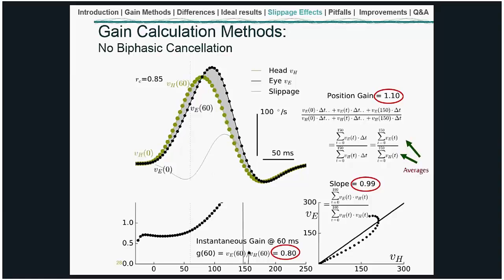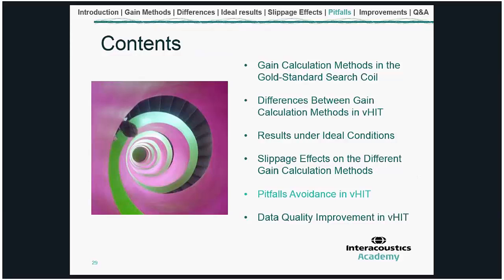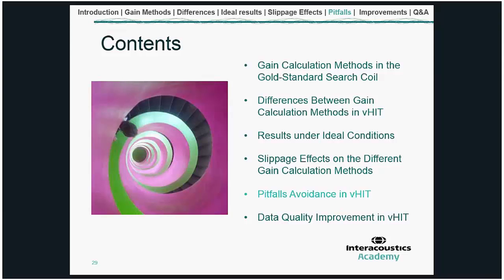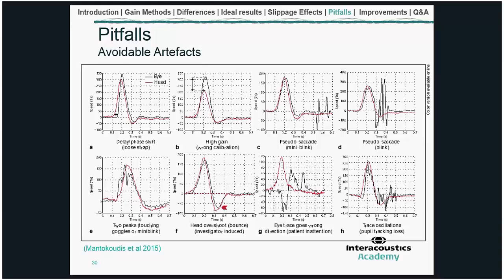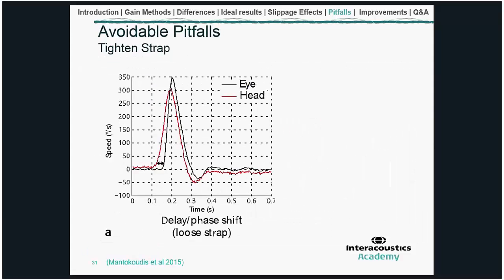In the next sections I discuss pitfalls in vHIT testing and how to avoid them. There is a nice paper by Mantokoudis who categorized different pitfalls, most of which are avoidable. One pitfall is a delay or phase shift between head and eye movement. If you see such a tracing, it is probably due to a loose strap on the goggles. The simple solution is to tighten the strap, remove and replace the goggles, and the phase shift should vanish.